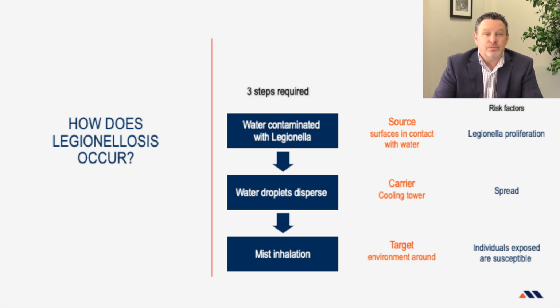So how does someone become sick? What's the method of transmission? It starts with a Legionella source. Cooling water becomes contaminated from the raw water. There is a mechanism of concentration, such as proliferation of algae or bacteria, where the Legionella count goes high. Then you have the transmission of the liquid water to the air, which is part of a mist formation. And that mist, which contains the Legionella bacteria, would get inhaled into the lungs.